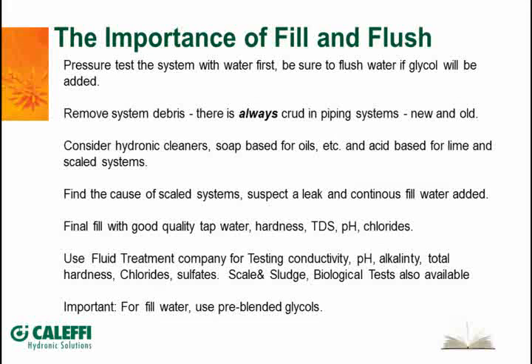But you can ask for a different blend. Typically you have to buy larger quantities. When I had the pre-blended glycol that I would buy locally, usually I would buy it in 55-gallon drums because the price went down, and then I'd have it for a few jobs, and they would blend it to my spec: how much, what percentage you want for freeze protection, and the additives they put in it also.